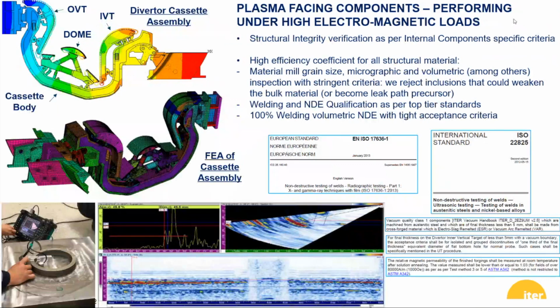And the way we deal with this is we have developed our own criteria for the structural design of the internal components, and we do thorough structural integrity verification of all our components. And we also have quite a lot of requirements for the quality of the material and techniques that are implemented in the fabrication of the internal components. For example, we have quite tight requirements for the micrographic examination and the volumetric non-destructive examination of the forgings or plates. We also have strong requirements basically to exclude from the material any trace flaw or any inclusion that could be a precursor for a leak path.